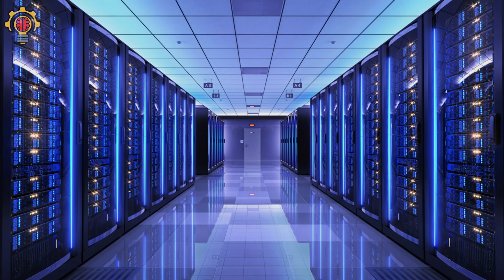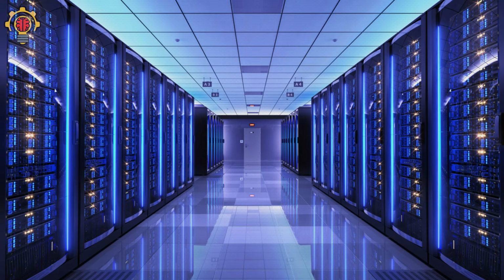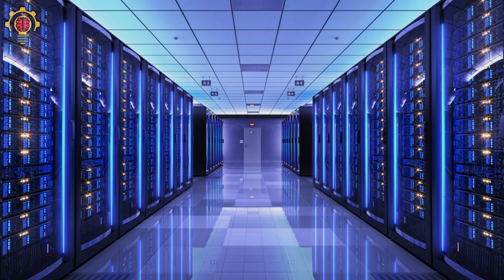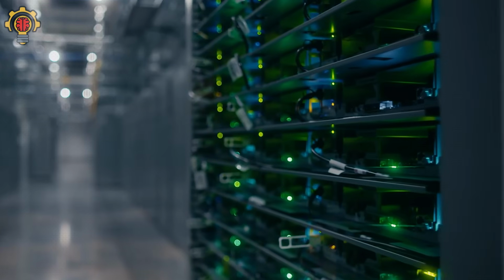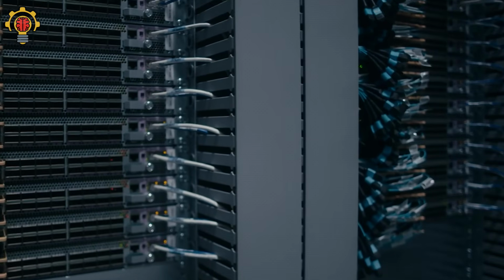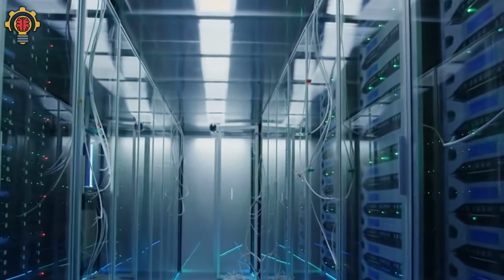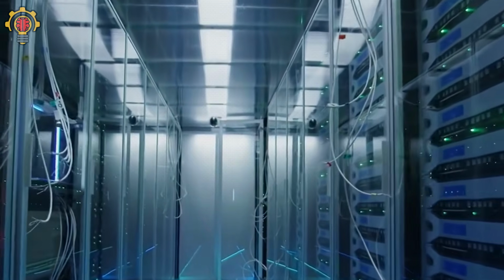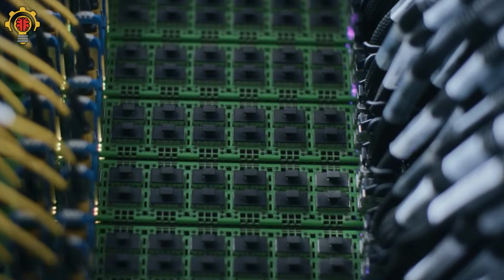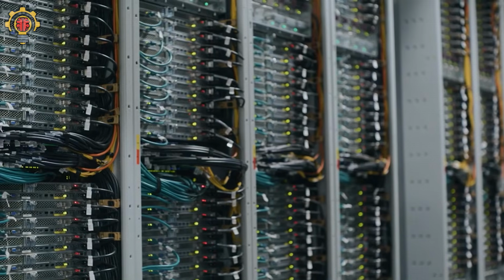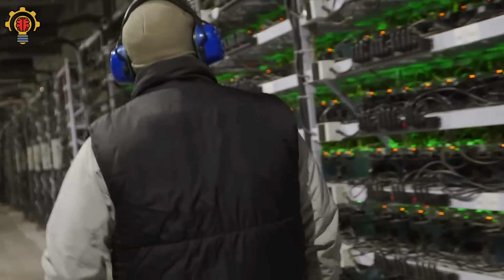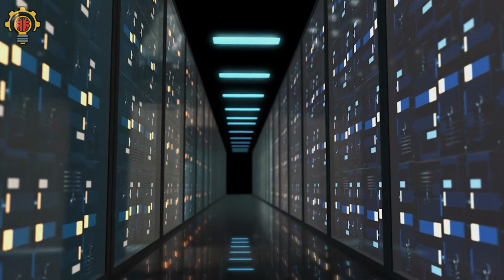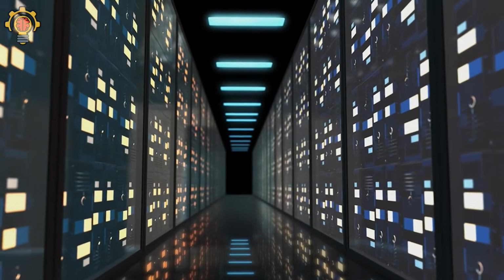Every Google search, every social media notification, every online purchase, every cloud backup, all move through systems like these. And every one of those systems generates heat. A normal person sitting quietly produces around 400 BTU per hour. But a single server rack can generate anywhere from 17,000 to over 102,000 BTU every hour. That amount of heat is massive. Now imagine hundreds or even thousands of those racks operating together inside one building without ever shutting down.